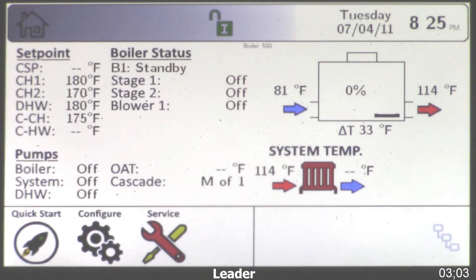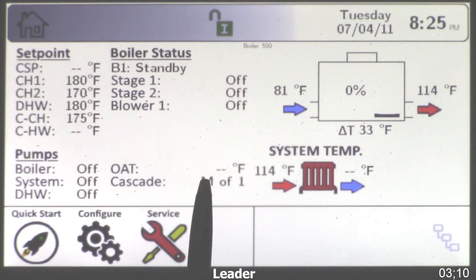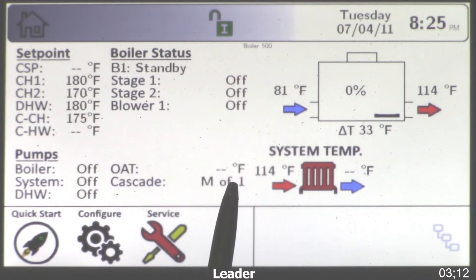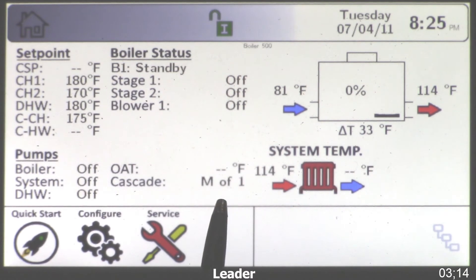Next we're going to go to the first lag boiler. I'm using two simulators, so right now we're showing under cascade that we're the master of one. This should read master of two — and why doesn't it? Because we haven't enabled the first member or lag boiler yet. So now let's go to that boiler.